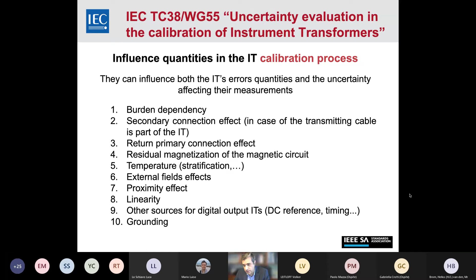Getting a bit deeper into the document, we have first considered all the possible influence quantities in instrument transformers from a calibration standpoint. In particular, the burden, the secondary connection, the return primary connection in case of current transformers, residual magnetization, temperature, external fields, proximity, linearity, and so on. There are others not written here, like grounding effects. We have tried to list and sort all the possible effects, and considered the most important ones.